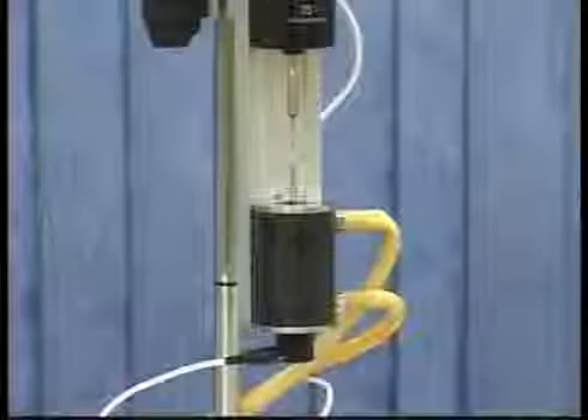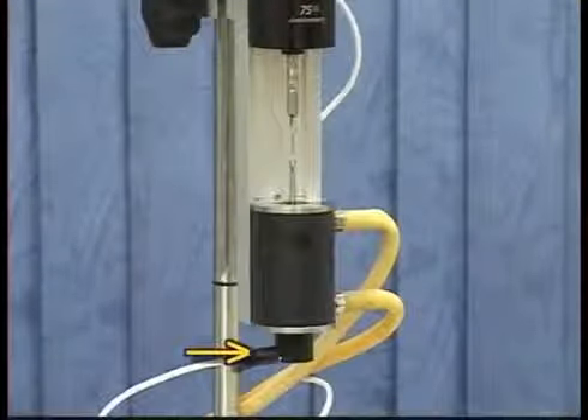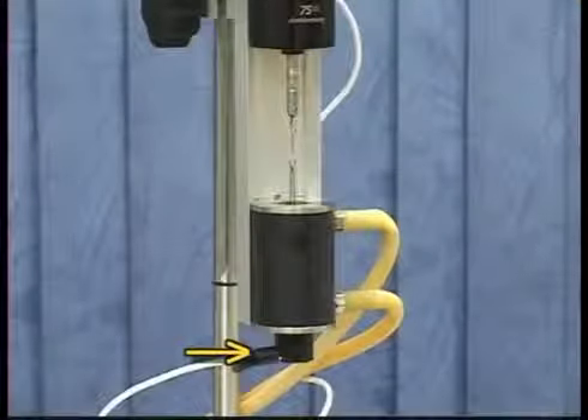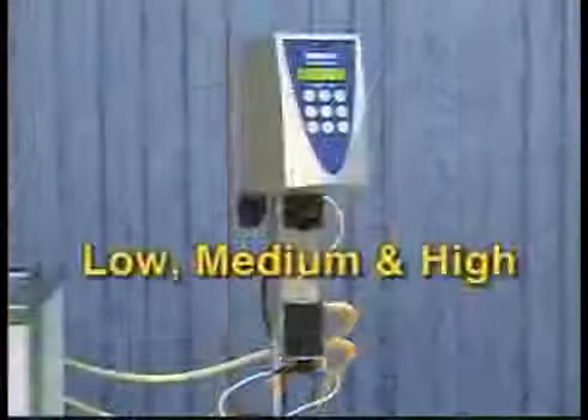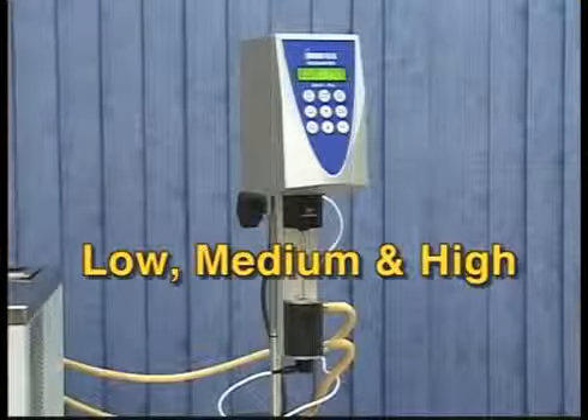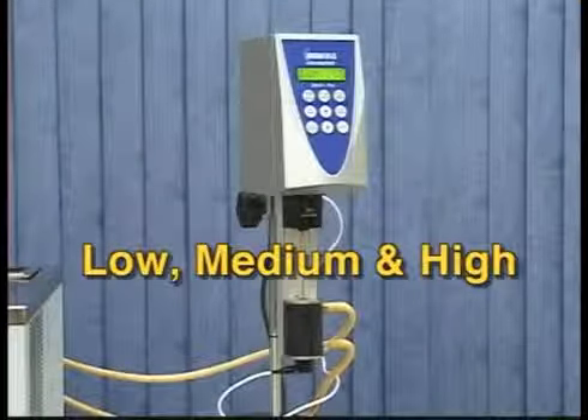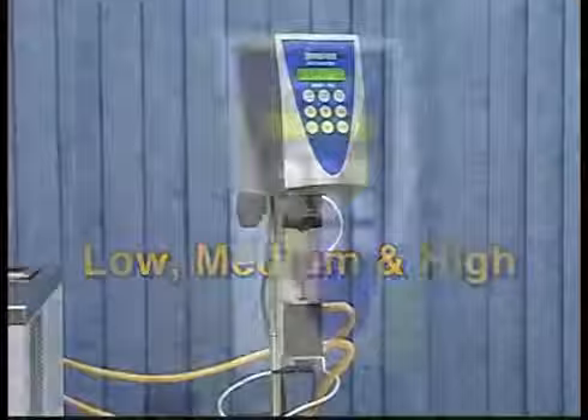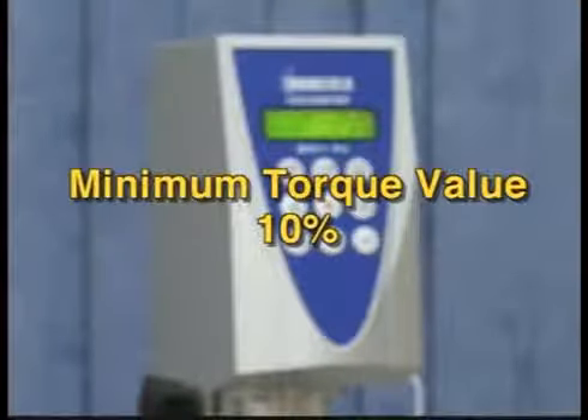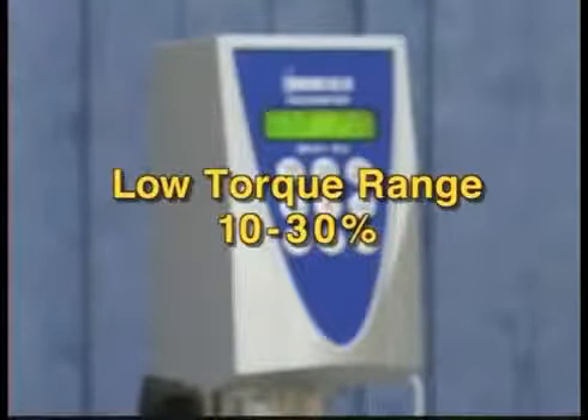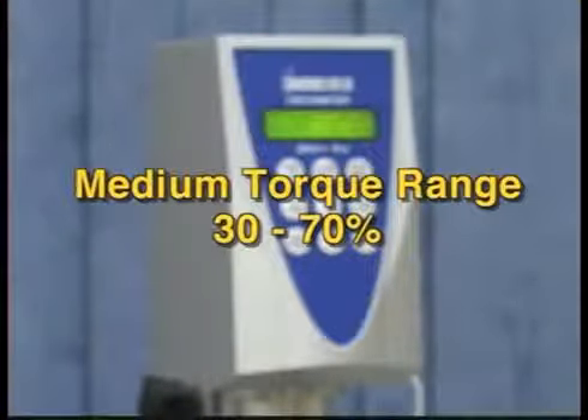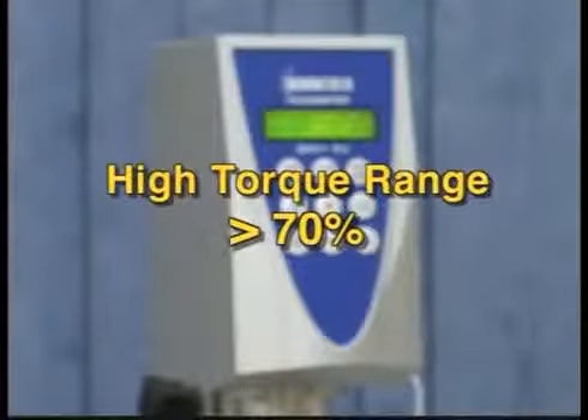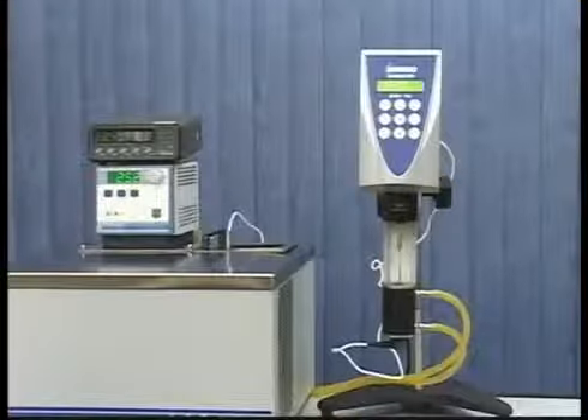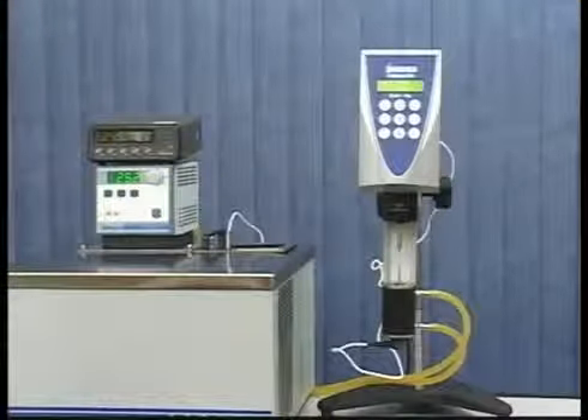The 13R chamber we are using supports a temperature probe, allowing for temperature monitoring at the instrument. Based on the spindle you will be using, select 3 speeds that will give you a low, medium, and high torque value. The minimum torque value for a good reading is 10%. A low torque range would be 10 to 30%. A medium range, 30 to 70%, and a high torque range above 70%. This will check the linearity of the spring on this instrument through its full range.